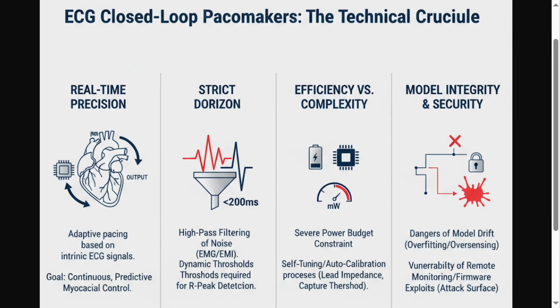Calibration problems? You mean long-term stability? Misha, these devices are supposed to run reliably for a decade. Human biology is messy and prone to decay. The electrode moves, the tissue fibrosis, the impedance changes. How does your closed loop compensate for the fact that the actual sensor environment is physically changing in a wet, corrosive biomechanical soup? That's where the unsupervised learning component becomes both necessary and terrifying.